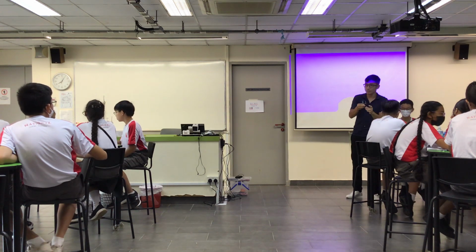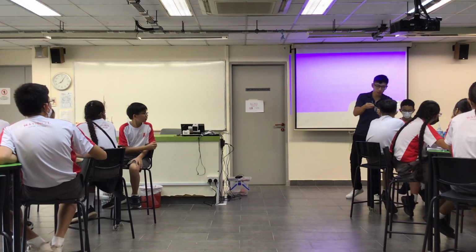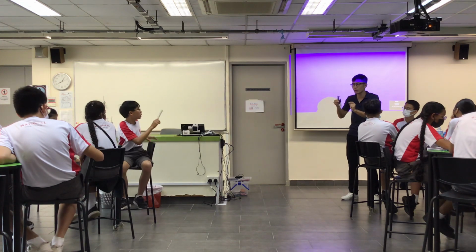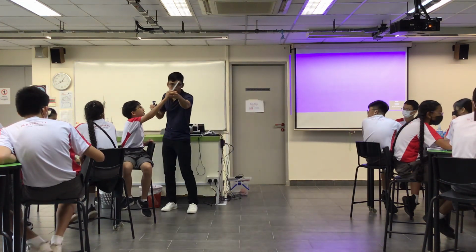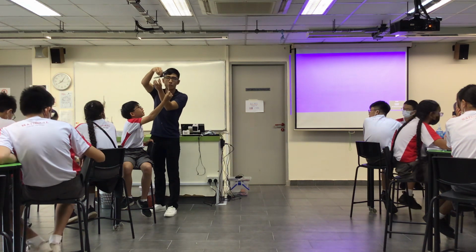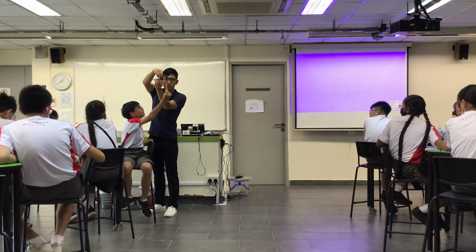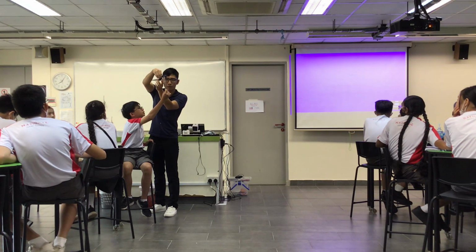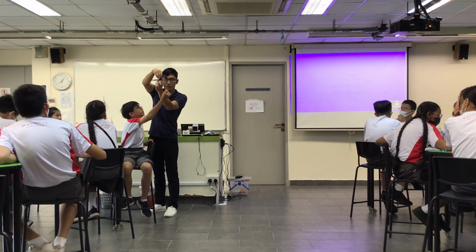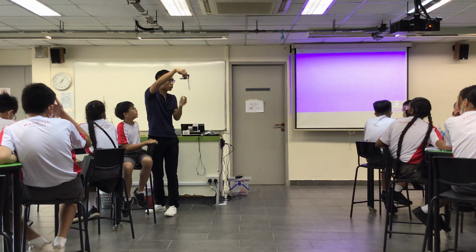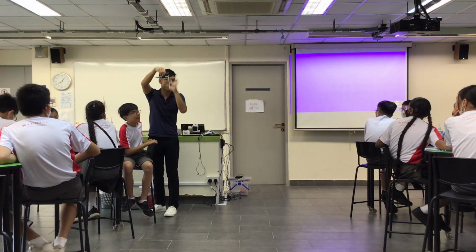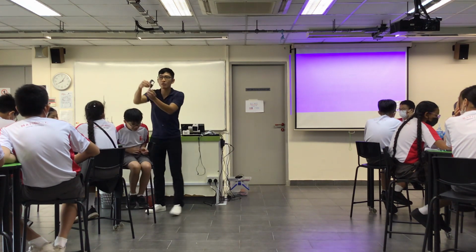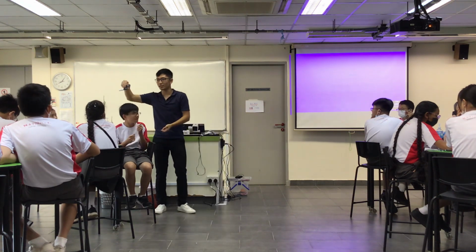Be extra careful. If I want to measure, let's say, the thickness of something, and you put something in between and start to close it, the moment you feel it touch, don't do it anymore. So Xavier, you raise your ruler. I'm going to now measure the thickness of this ruler. I'll put the ruler in between and slowly close it. But the moment I start to feel some tension, I'm going to stop. Oh, okay, I feel the tension. Xavier, let go. And it holds. Don't try to squeeze it anymore. The harder you squeeze, you will damage the sensors. But this instrument measures very thin things. I cannot possibly measure Xavier's head this way.